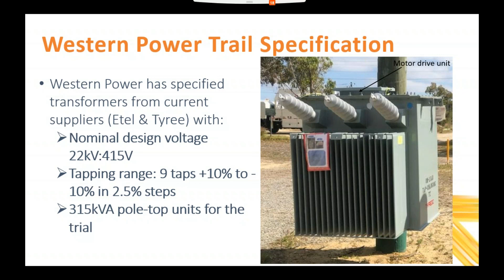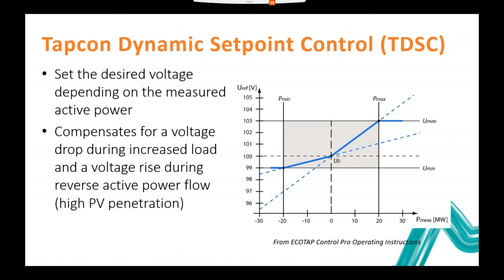We also looked at using what MR calls a TAPCON dynamic set point control, or TDSC. This is effectively a real power droop function, and what that means fundamentally is, if you are pushing really big amounts of forward real power, you're going to have a voltage drop because of all the load, and the control system will push the voltage of the transformer up to allow for that voltage drop. Conversely, if you've got reverse power going to the transformer, you'll have a voltage rise, and hence what you want to do is drop the voltage of the transformer to the lowest possible voltage to allow for a voltage rise along that feeder. That's one of the methodologies that we used. So that's just one being constructed.